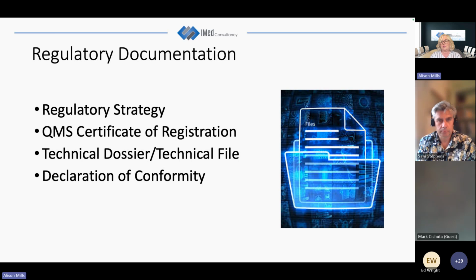And then you've got the technical dossier or technical file, which includes all of the documents that prove all of the technical details of your product. That'll be a summary of what the product is and what it does, the materials that have been used and specifications, your risk management file, your design history file, and your clinical evaluation of the product or products like it. There's a literature search where we look at other products which may be equivalent and what the experience of those products has been, because if those products have had issues with safety, then they're things you need to think about.